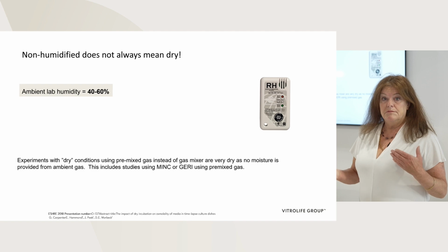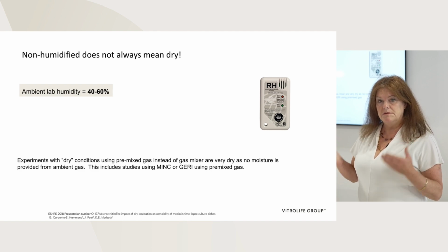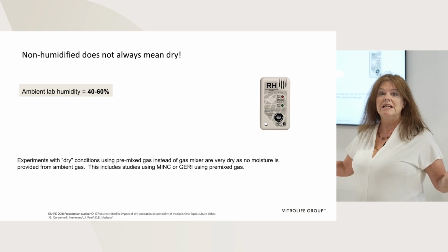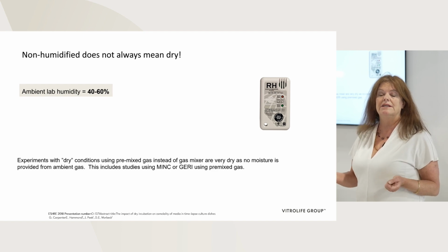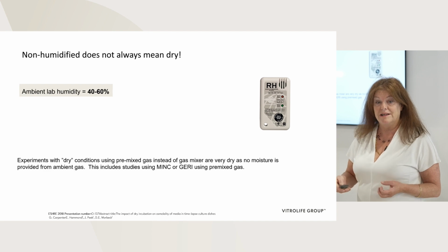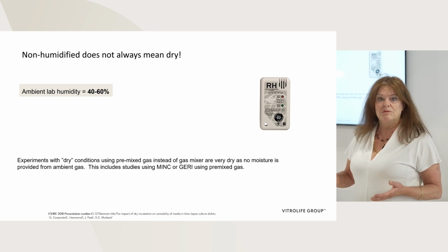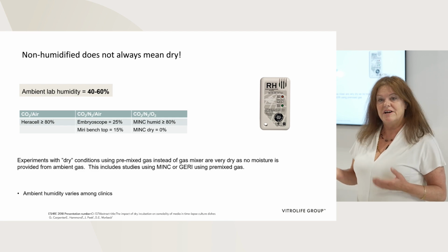So in fact, incubators that are non-humidified does not mean dry. If you're using a type of incubator that has a gas mixer, it's taking some of the ambient air. So a proportion of the humidity in the ambient air is in fact incorporated in the incubator. So it's not totally dry, versus if you're using an incubator with a premixed gas, then you really do have a dry environment.